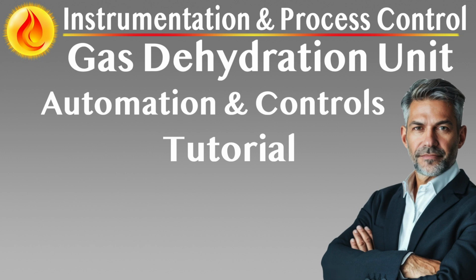Level monitoring. Although the reboiler uses a weir-type overflow, low-level alarms detect interruptions in feed. Stripper gas flow, if present, is controlled via a simple flow loop monitored by rotameter or differential pressure transmitter. Protective functions and alarms.